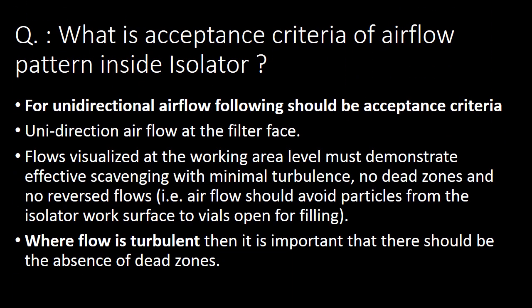Next important question: what should be the acceptance criteria of airflow pattern inside the isolator? For unidirectional airflow, airflow should be unidirectional at the filter face. Flows at the working area level must demonstrate effective scavenging with minimal turbulence, no dead zones, and no reverse flows.